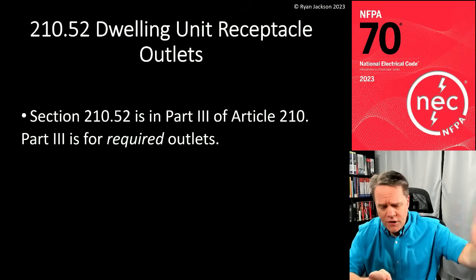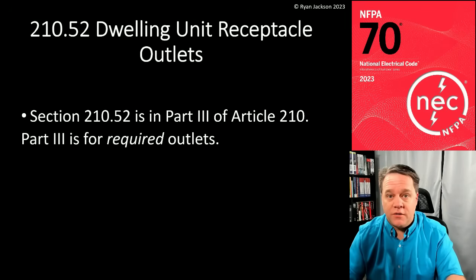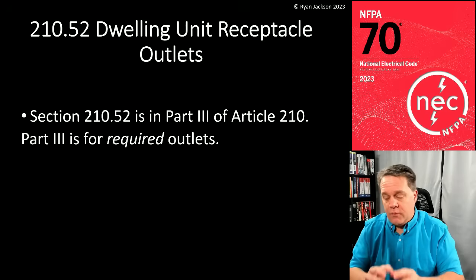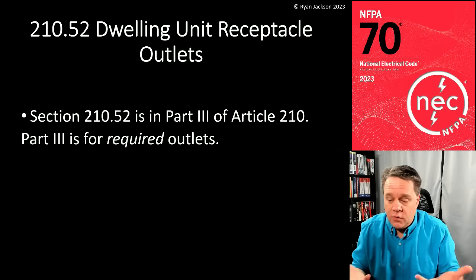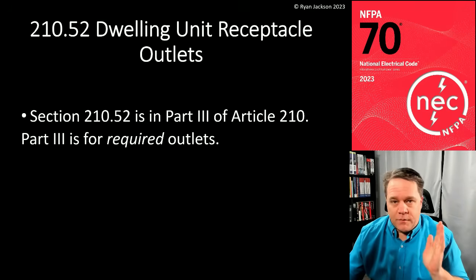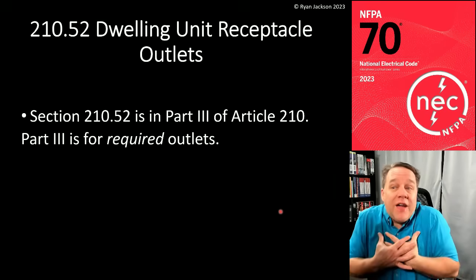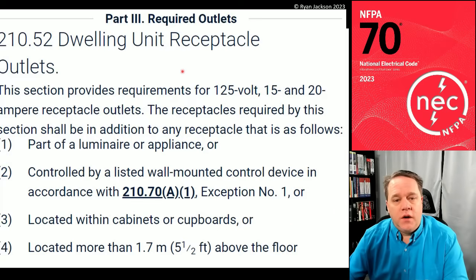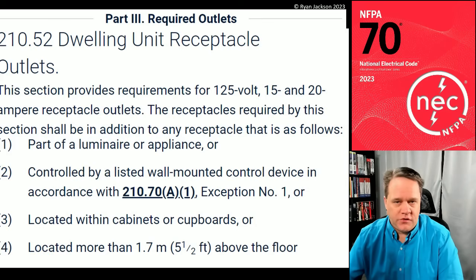We start with Article 90.2 — the scope of the code covers installation of conductors and equipment. If you're installing something, you need to keep reading. We go to Article 210 because we're installing a branch circuit, which starts at the last breaker or fuse and ends at the utilization equipment. Part Three of Article 210 covers required outlets — these are the rules for the receptacles you are required to install.